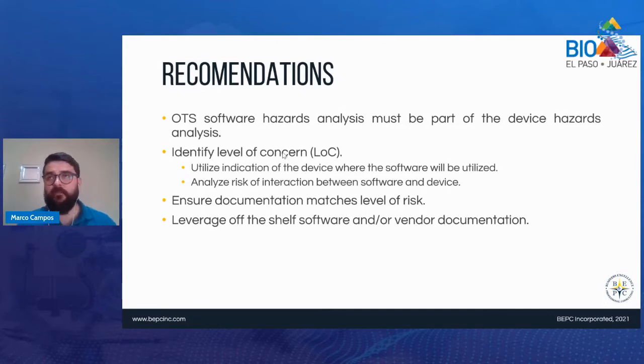We recommend that if you have this type of application and you want to implement it and make sure your validation is going to meet regulations and be within compliance, you need to marry your off-the-shelf software and its hazards analysis with your device hazard analysis.